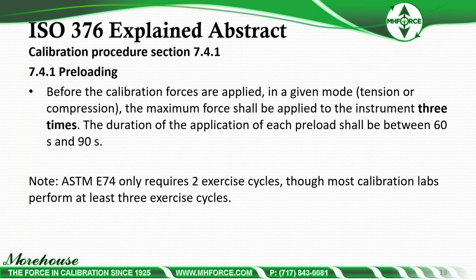Calibration procedure per section 7.4.1. Before the calibration forces are applied in a given mode, tension or compression, the maximum force shall be applied to the instrument 3 times. The duration of the application of each preload shall be between 60 and 90 seconds. The only thing different here is ASTM requires only 2 exercise cycles, though most calibration labs, and we recommend it to them, perform at least 3.